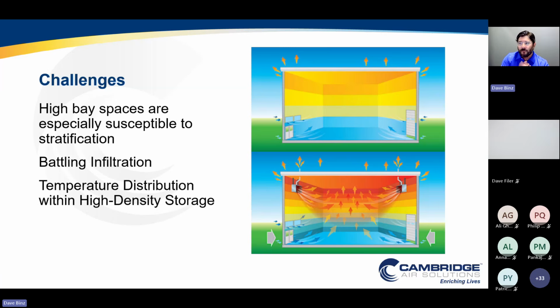When we look at high bay space for a warehouse, it's fairly similar to what you see in the manufacturing space. But now, since I don't have high process exhaust requirements, the building changes a little bit. In the warehouse space, high bay spaces are very susceptible to stratification. As hot air rises, getting that heat to the floor, to the operators working at the floor, can be a challenge. And without looking at how we deploy certain technologies, pressurization can cause an impact to your HVAC system. Also, we're constantly battling infiltration.